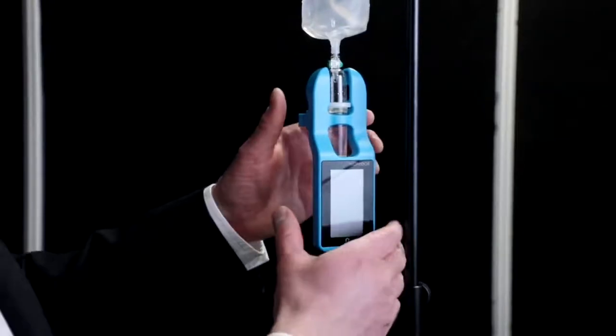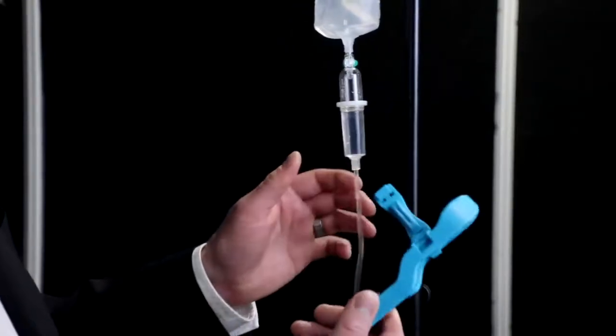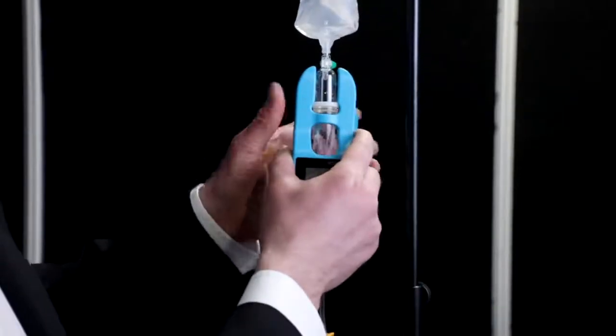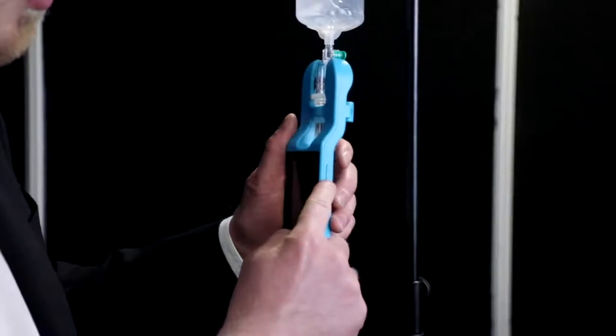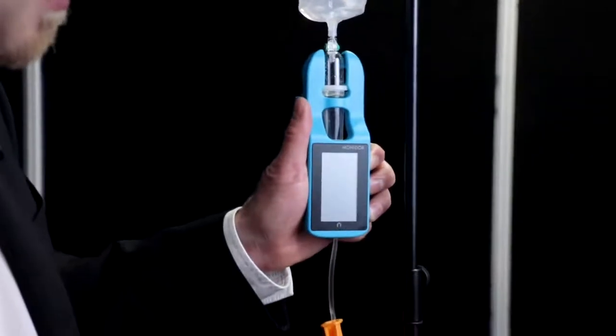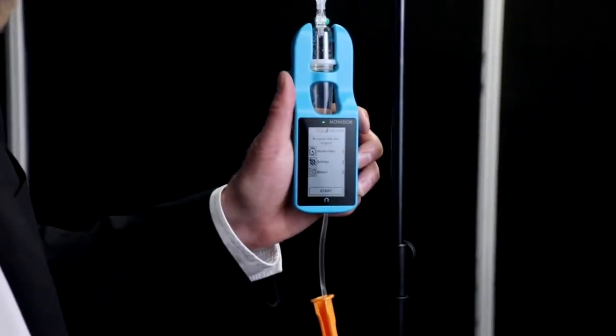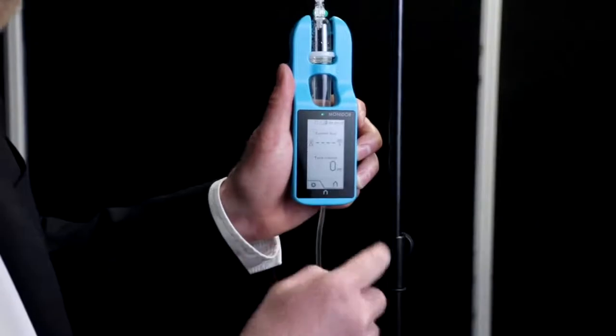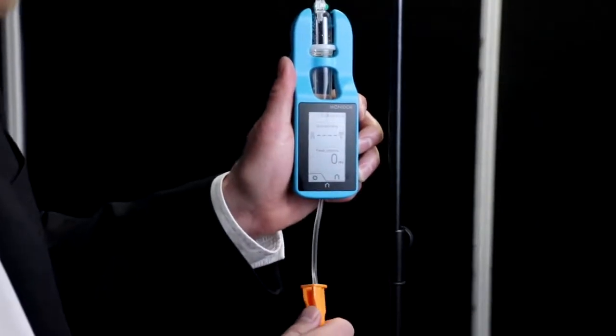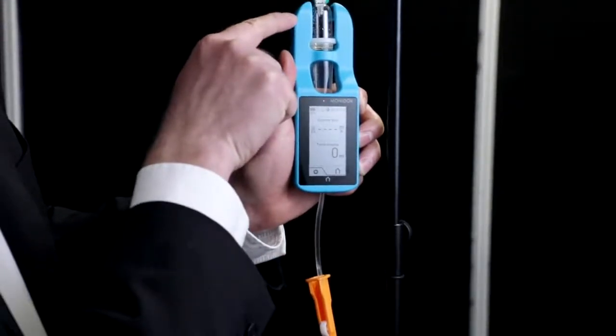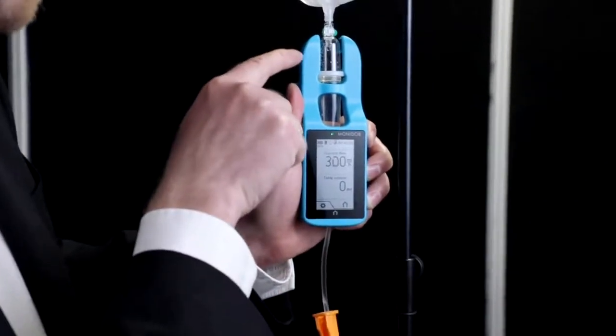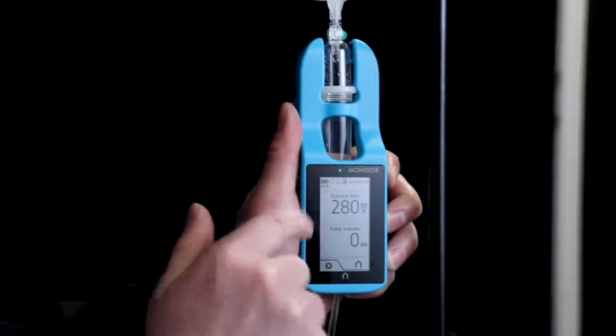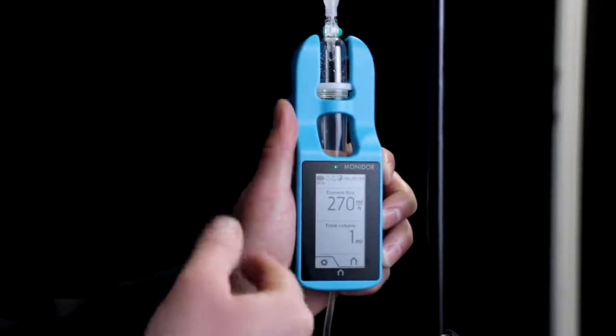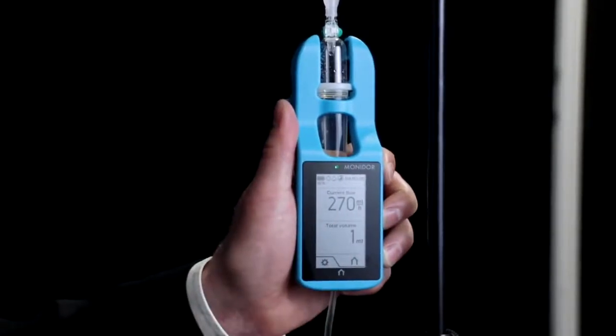Monidor can be clicked to the gravity set like this. The device can be switched on with this button, power on and off, like this. By pressing the start button, it starts calculating drops with an optical eye. Once it has detected three drops, it will show flow rate, and after that it will update the flow rate after every drop.